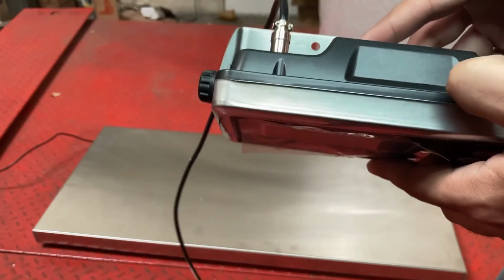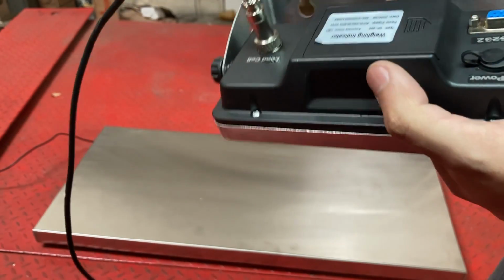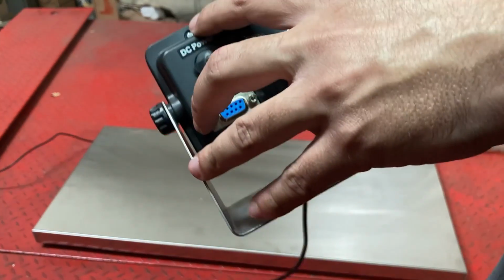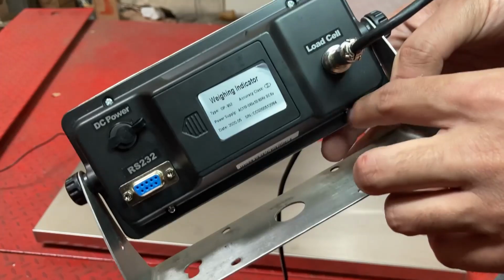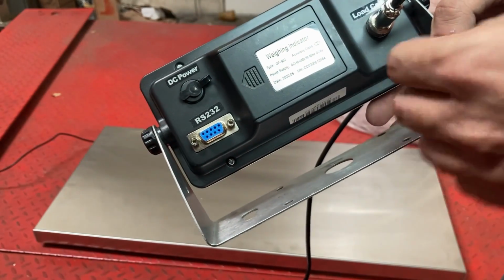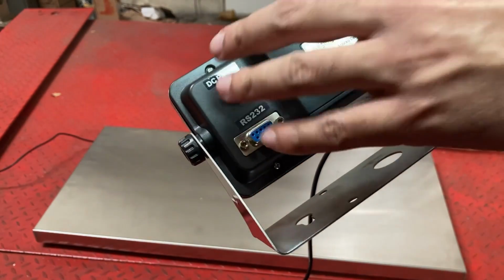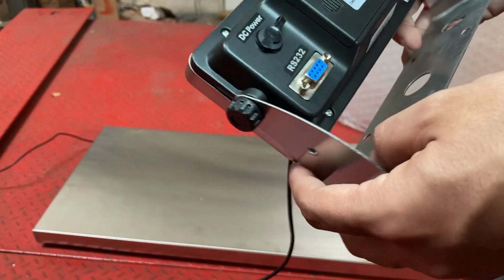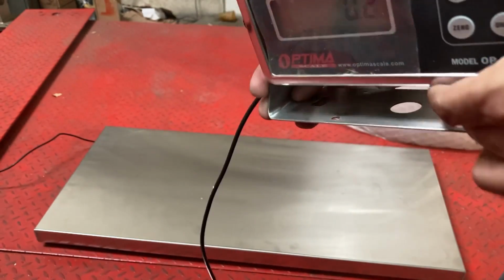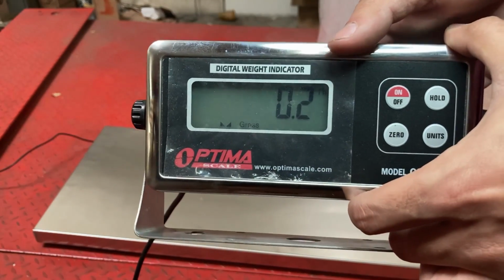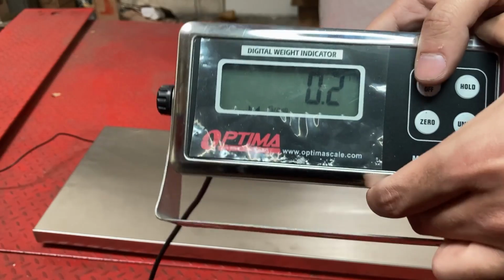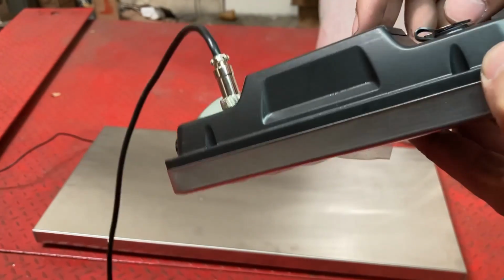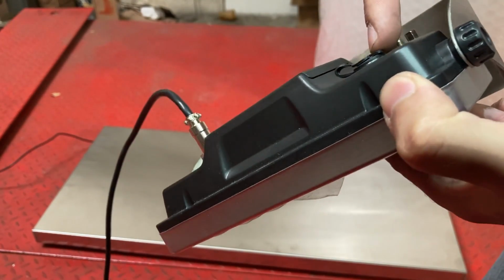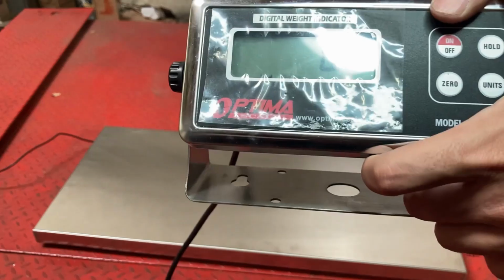I do have another video on how to check the connections internally, but you'll see there are 4 screws holding it in. So maybe the keypad one disconnected inside. Go ahead and open it up and check if all the connections are fine. I have another video on that. But if you find the 902 does not turn on and it's not reading anything at all, and you change the batteries, you plugged it into power, it still doesn't work, so maybe the 902 just failed.